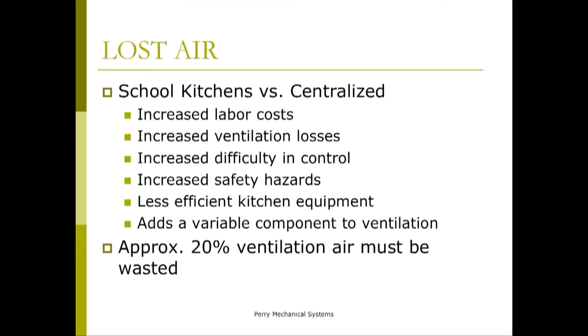With the other air that we can recover, what can we do with it? We can bring it back into the building through energy recovery. I'll show a diagram in a second, but with this equipment we can get about 70% effectiveness. You take your exhaust stream and pass it by the intake stream, recovering that energy before it exhausts out of the building. Obviously you don't want to cross over all the air, because you don't want those contaminants that you have to exhaust out of the building. The heat exchangers that do this transfer are why it's only 70% effective instead of 100%.